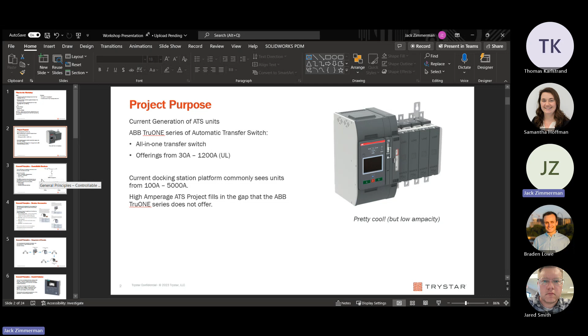So, general principles, an overview of how this unit works and what we're working with here. At its core, the high amperage ATS uses two breakers to act as a switch between two sources and the load. In this diagram we have source 1, source 2, and the load. We can open one of the breakers and close the other to have the closed breaker source feed the load. We can also have both breakers open, which is nice if you have no sources available. But you cannot have both breakers closed, obviously, and that's the common concept within our one line of interlocking. This is the basis of the high amperage ATS system.